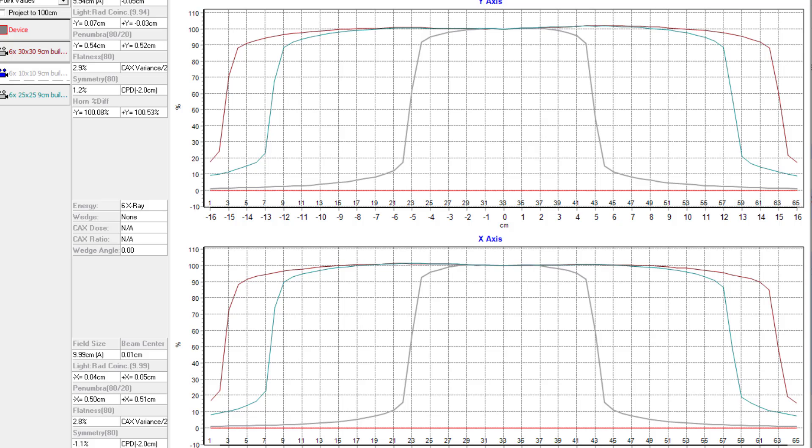Symmetry, they specify less than 2%. For electrons, it's different. Symmetry is still 2%, but the flatness can be as high as 5.4%.